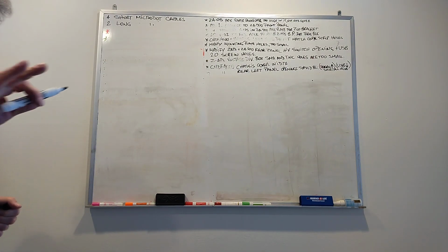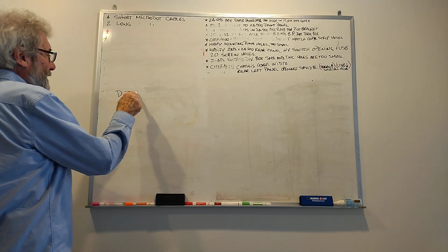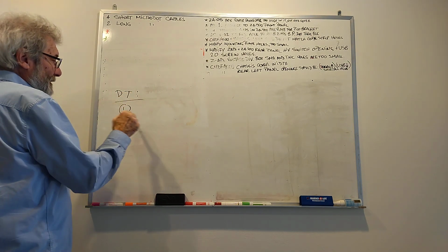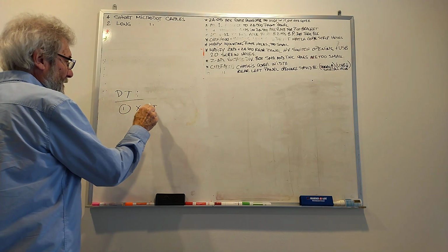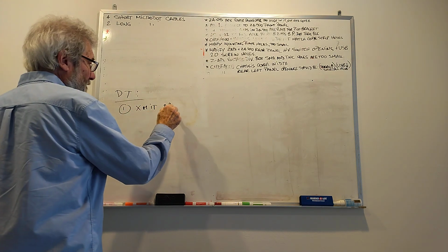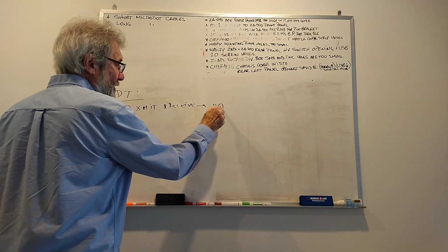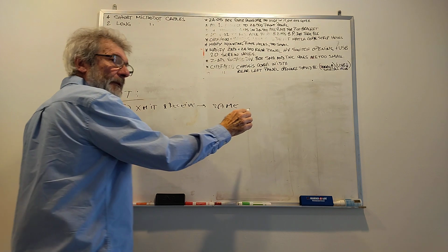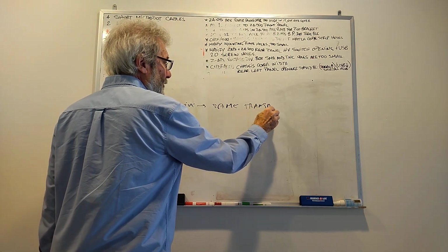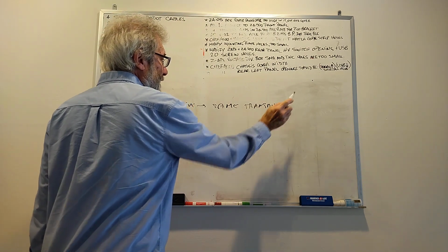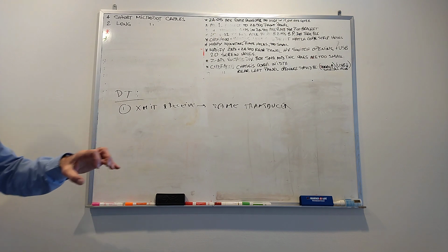Talking about DT first, to revisit it, very important: the advantages that we have. One, as I said, transmit and receive in the same transducer. Instead of through transmission, two different transducers.